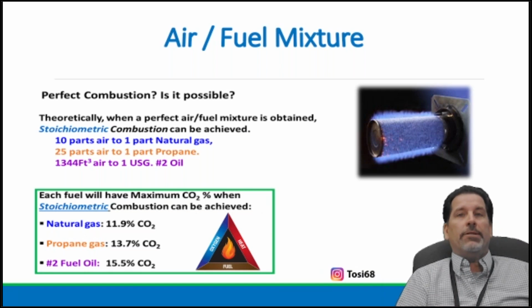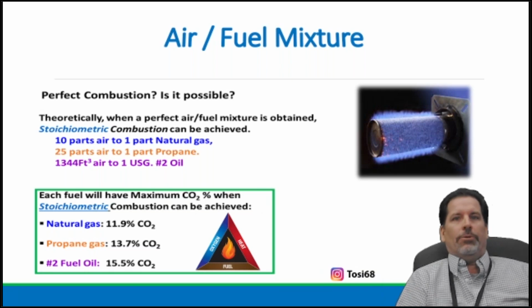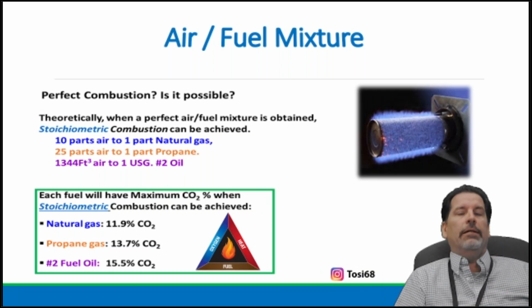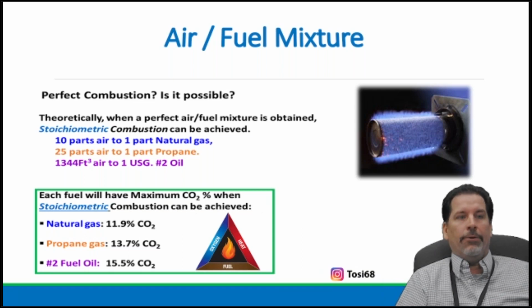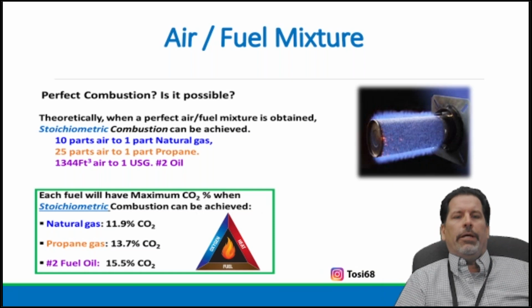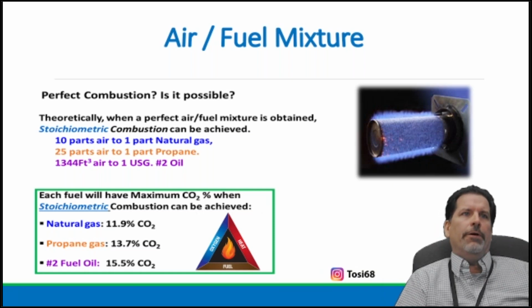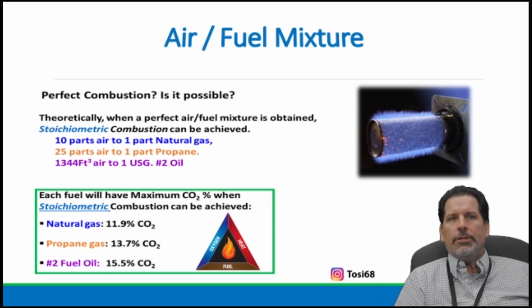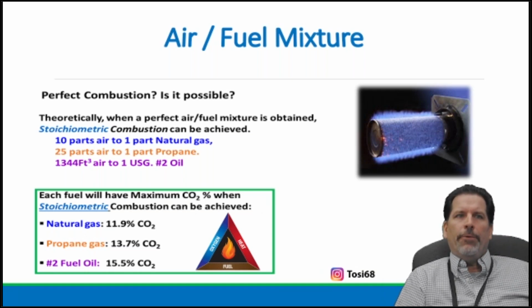There are differences in what makes up natural gas coming from, let's say, Texas or wherever, through the pipeline, and what's actually being delivered in a truck, whether it be propane or fuel oil. So the perfect scenario of parts per million of air to fuel for natural gas, propane, yeah, it is achievable. It's called stoichiometric, right? So there's another guy who came up with this whole process of learning how we get perfect combustion. And it really plays well with maximizing our CO2. The problem is if we max everything out, you see, we were looking for 9 before. The perfect combustion is 11, almost 12 here.